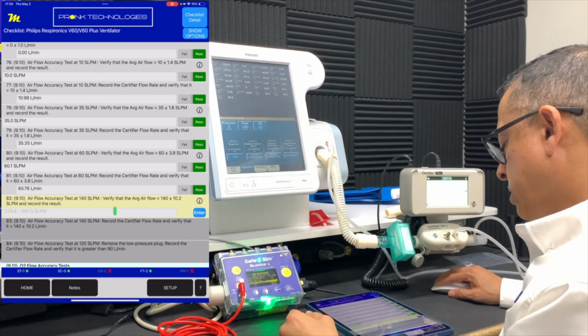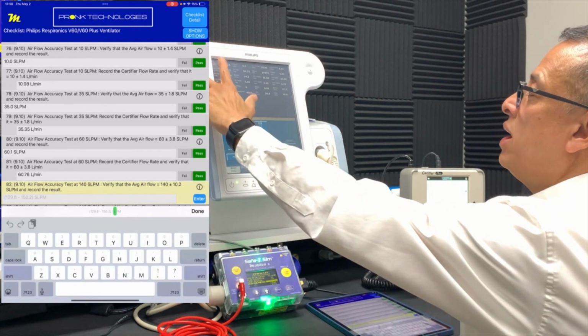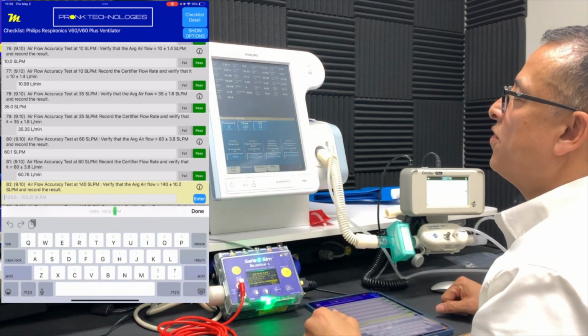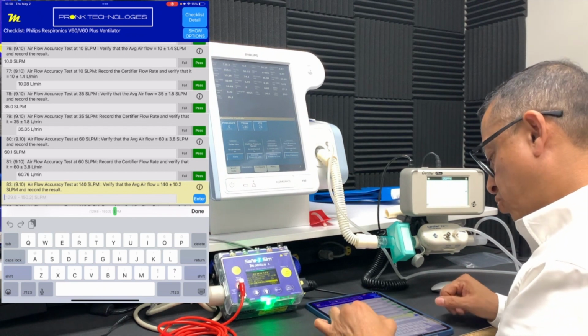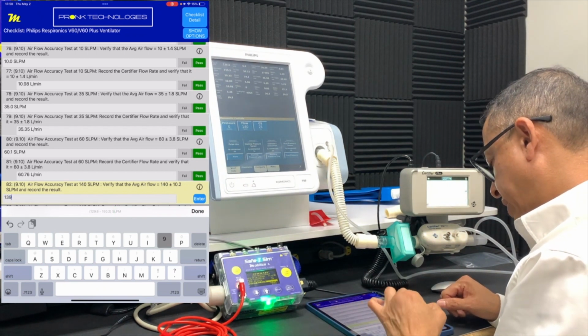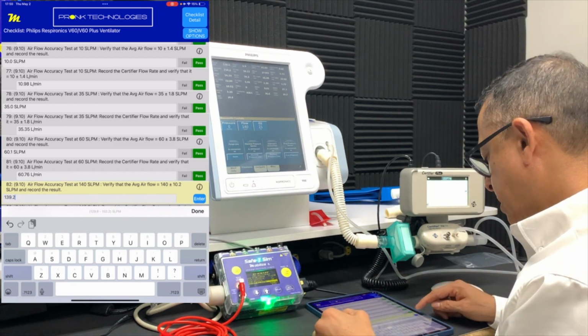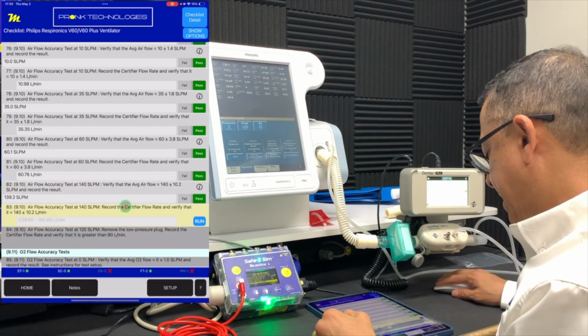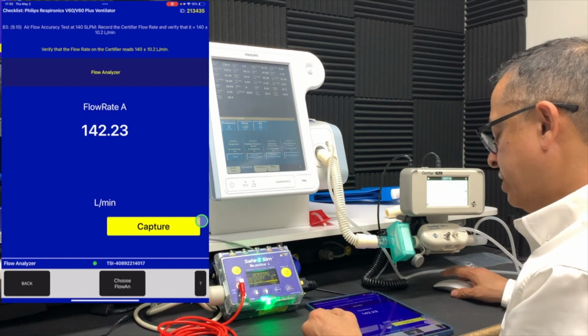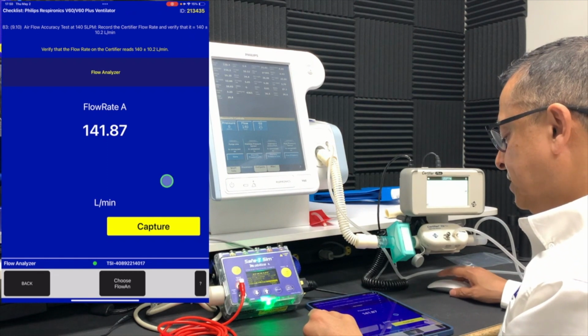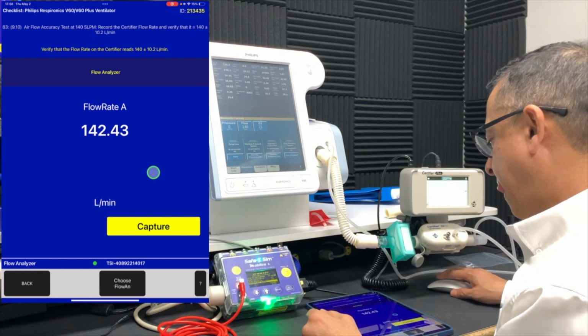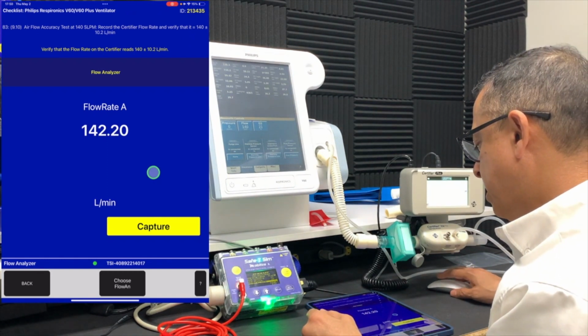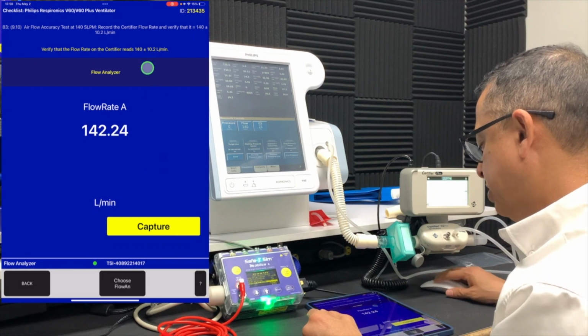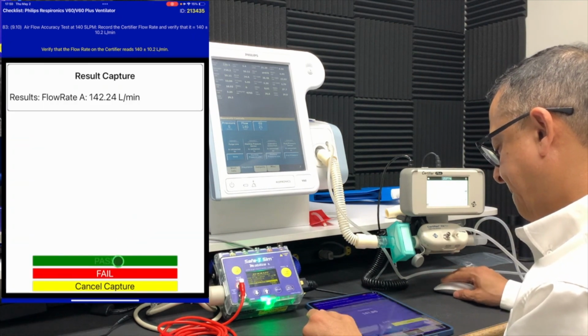140, we're measuring 142.2, we'll call it. Pretty accurate. Capture that result, and then once again, the certifier, what does it measure? It's measuring slightly higher, but within tolerance. We want to be within plus or minus 10.2, so well within.